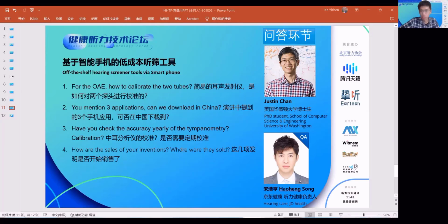You might ask, okay, how often do you need to calibrate it? For our study, we calibrated it once and it worked for about 3 months. We didn't have to keep calibrating it. But how do you know if there are issues with the calibration? Typically, in a real commercial device, you would take a measurement in open air, just no ear, just in open air. And there should be 0 OAEs. And you should also put it in a tube, and there should also be 0 OAEs. So if you perform those tests and they do not work well, then you have to recalibrate the sound level volume. But we think maybe this is something you have to do maybe every 6 months or every 12 months. So it's not a frequent process. Does that answer the question?